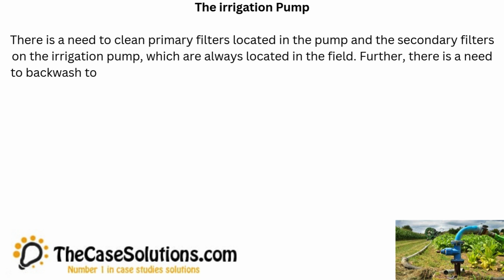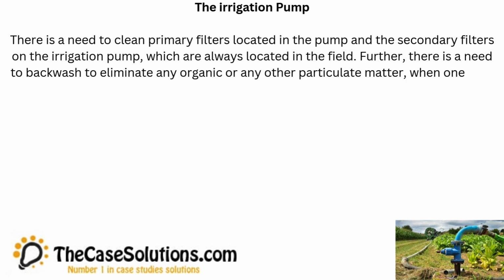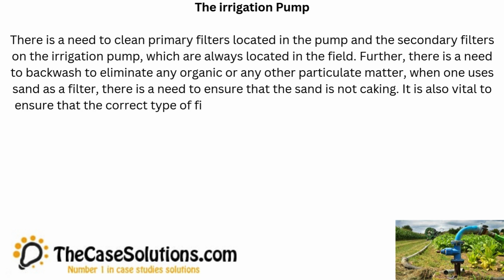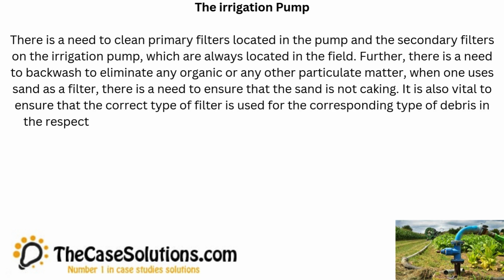Further, there is a need to backwash to eliminate any organic or any other particulate matter. When one uses sand as a filter, there is a need to ensure that the sand is not caking. It is also vital to ensure that the correct type of filter is used for the corresponding type of debris in the respective water source.